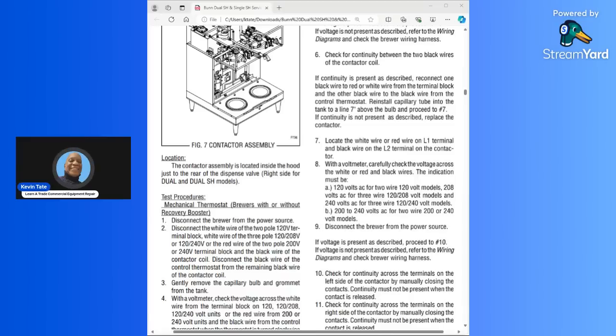So what they're saying is when you reinsert that capillary bulb from the thermostat, you want to go about 7 inches above the bulb, and then you can proceed on to the next step. If continuity is not present as described, replace the contactor.